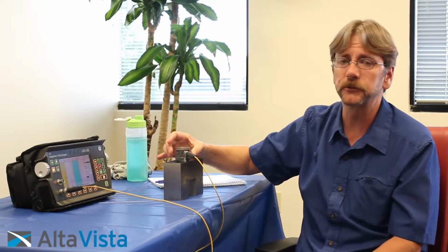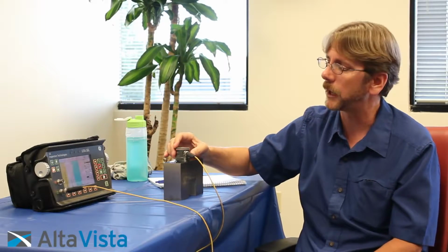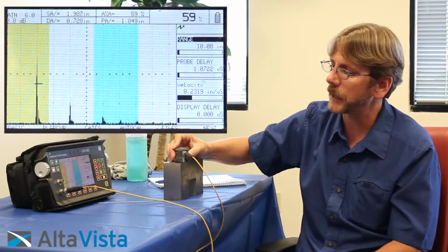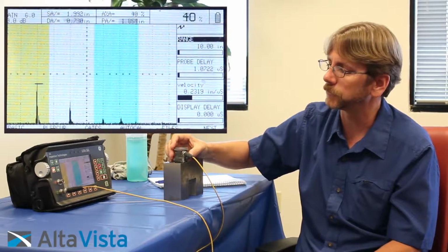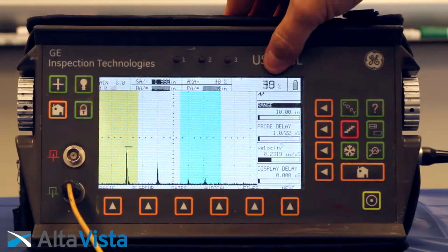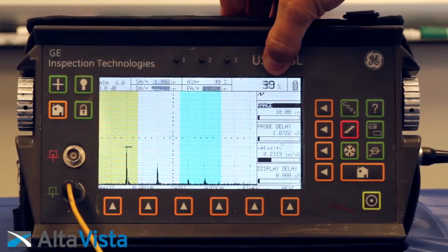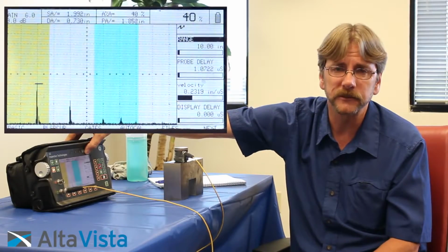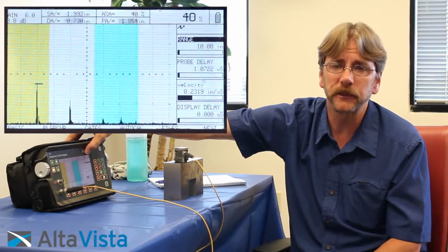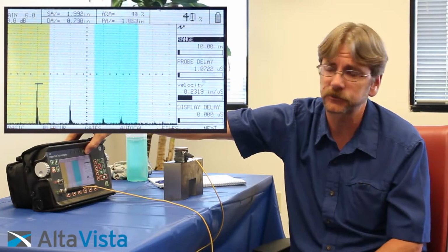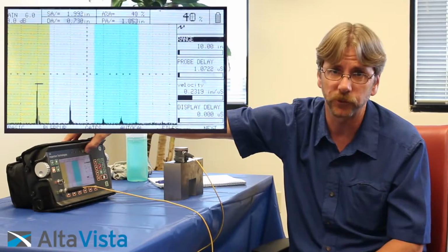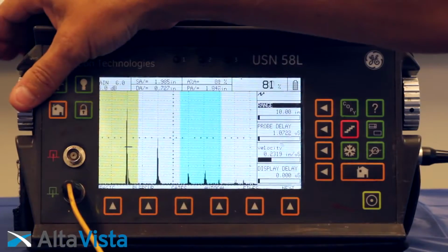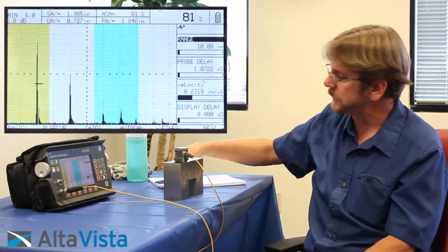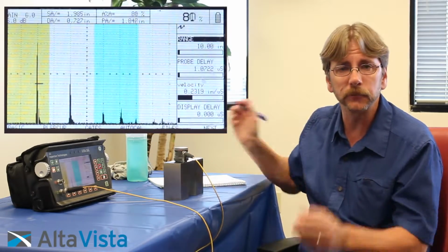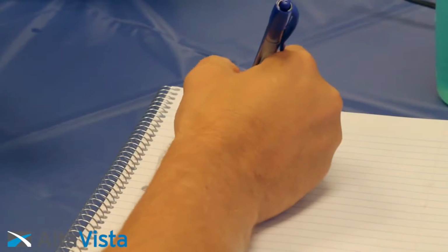So we're going to take the transducer and slide it towards the long portion of the block until we decrease it by half. In this case, we're going to go to 40% full screen height, also now indicated right where my thumb is at. And then we're going to increase the gain by 6 dB. When we increase the gain by 6 dB, we effectively double the signal strength. So this 40% screen height should go to 80. In this case, it goes to 80. And we're going to record that value, and we're going to walk through that step several times over a 60 dB range.